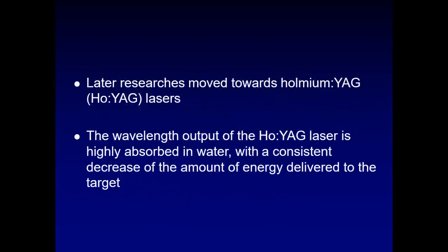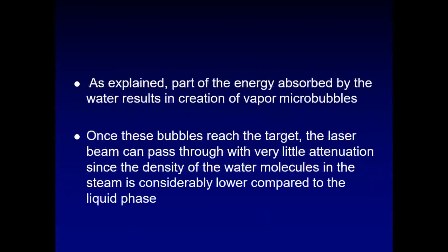Later researchers moved to holmium YAG lasers, and the wavelength output of the holmium YAG laser is highly absorbed in water, with a consistent decrease in the amount of energy to the target tissue. As explained, the part of energy absorbed by the water results in creation of vapor microbubbles. Once these bubbles reach the target, the laser beam can pass through with very little attenuation, since the density of water molecules in the steam is considerably lower than in the liquid phase. So that is why they shifted from blood to 50-50 saline and blood, and then to water.